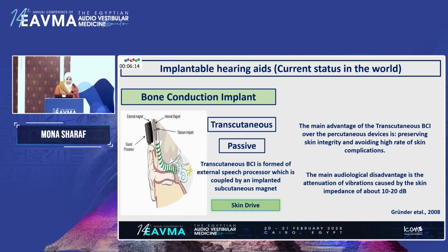The passive transcutaneous implant is formed of an external speech processor which is coupled to an implanted subcutaneous magnet. So here the skin is intact, and that's why it's called skin drive. The main advantage of the transcutaneous bone conduction implant over the percutaneous one is preserving skin integrity and avoiding the high rate of complications associated with the percutaneous bone conduction implant. However, the main audiological disadvantage is attenuation of the vibrations caused by skin impedance of about 10 to 20 dB.